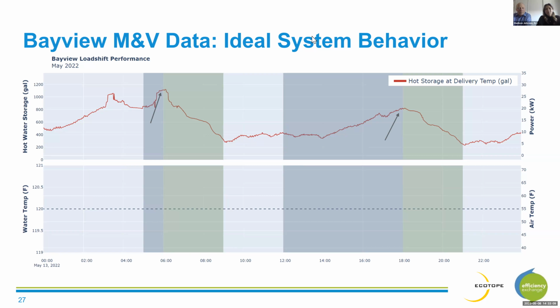And so here, one important thing to note is that as we enter our shed period right after loading up, we reach a maximum in our hot water storage. And then as we exit the shed period, we reach a minimum. And so this means as soon as our shed period is over, we're immediately starting to generate more hot water. You may notice that as we enter the morning shed period, we reach around 1,100 gallons of hot water in our storage tanks. But as we enter the evening shed period, we don't quite reach the same levels.